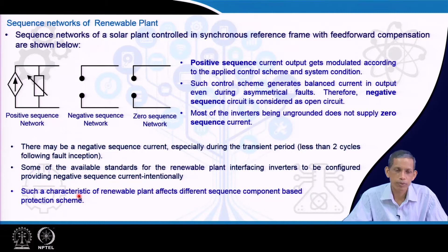One important factor is the transformer connections. We see two stages of stepping up the voltage, the first stage and the second stage, and the corresponding transformer connections are Dy11 and then Yd11. It means that the angle shift at the first stage and the second stage gets cancelled out by these two transformers, and that is maintained.